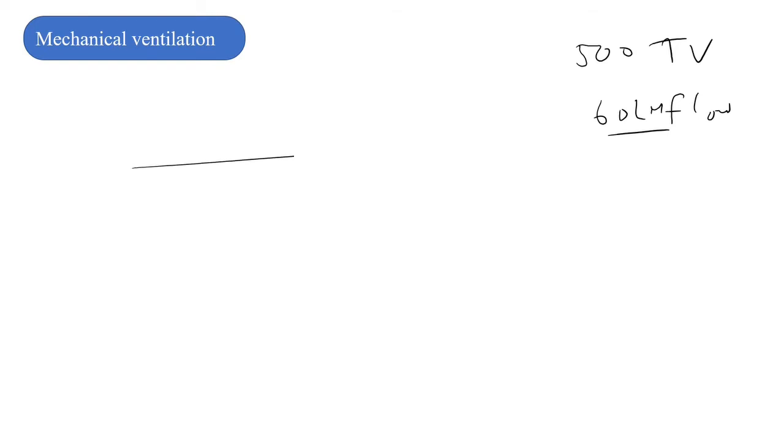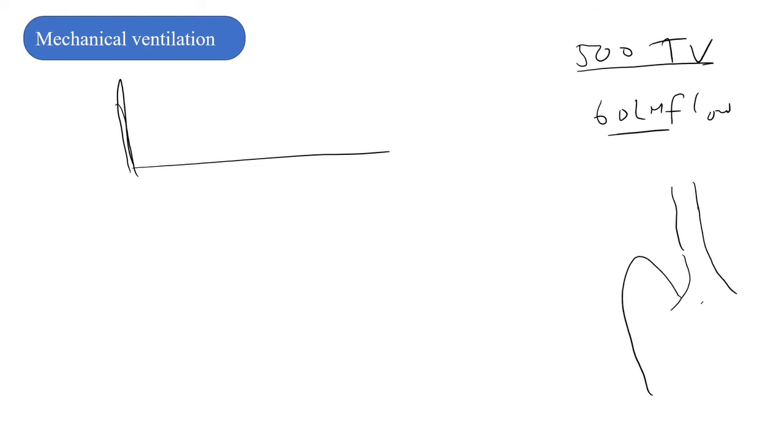When you revise the pressure curve, giving this tidal volume will result in an increase in the proximal airway pressure. Basically, the ventilator will measure the airway pressure at the presence of the sensor, the proximal airway pressure here. So it will increase to a peak level, and the rate of increase will depend upon the flow rate.